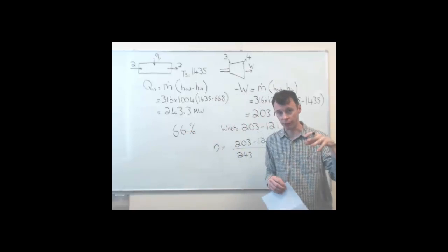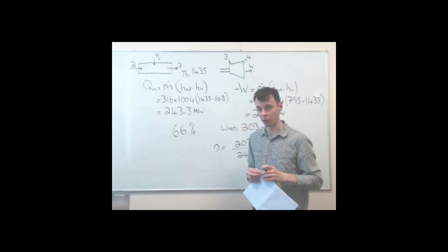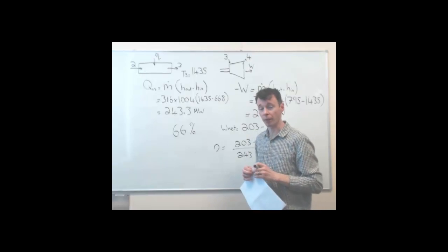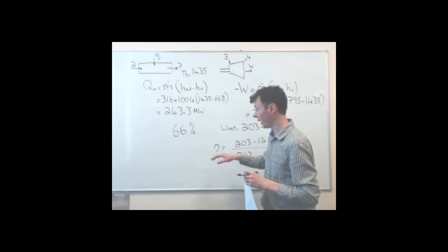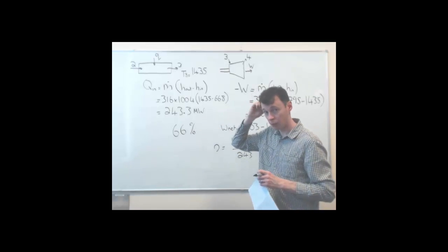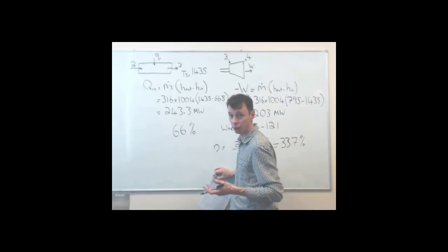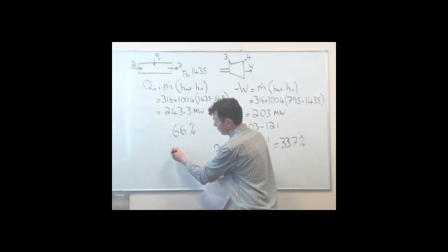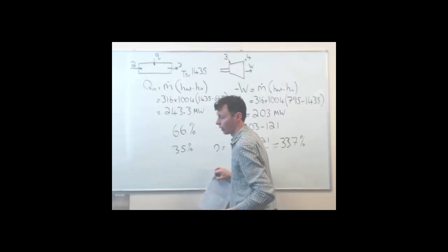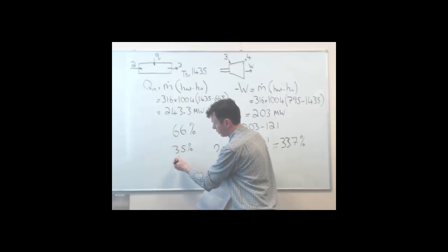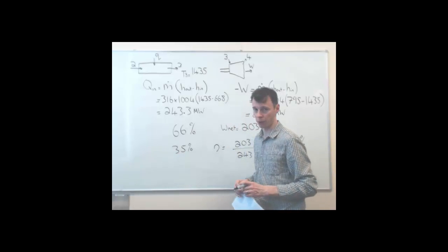So the nearest one to us here in University of Southampton is in Marchwood, over the other side of, just opposite the port. It's an 800 megawatt power station. It was constructed inside a year, very, very quickly, and it has a station efficiency of about that. Compare that to standard Rankine cycle. So the best coal-fired stations are about 35% efficiency, and the best nuclear sites about that or slightly lower, so about 33-35%.